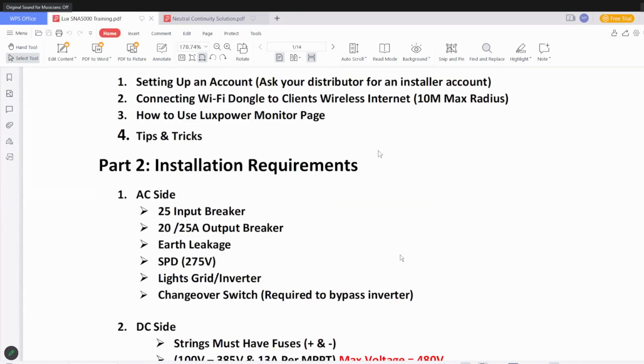So the installation requirements that we recommend from the AC side: we recommend a 25 amp input breaker, and a 20 to 25 amp output breaker as well. With regards to the earth leakage, which will also include the neutral and earth bonding, I'm just going to show you guys a quick diagram.